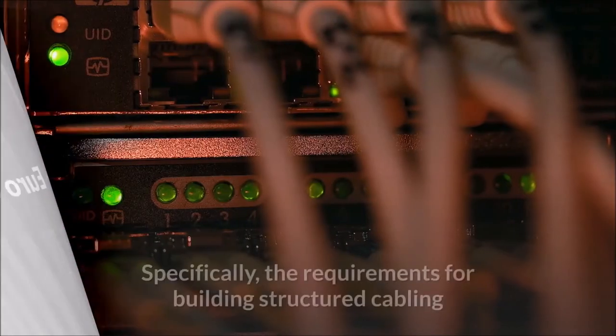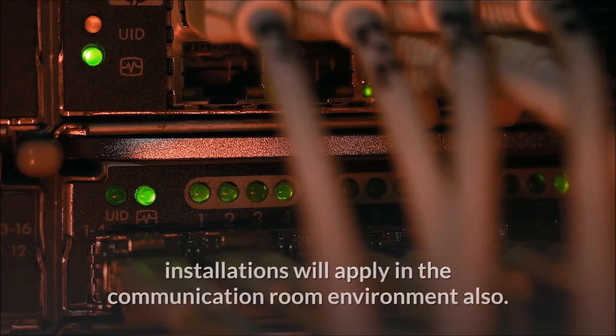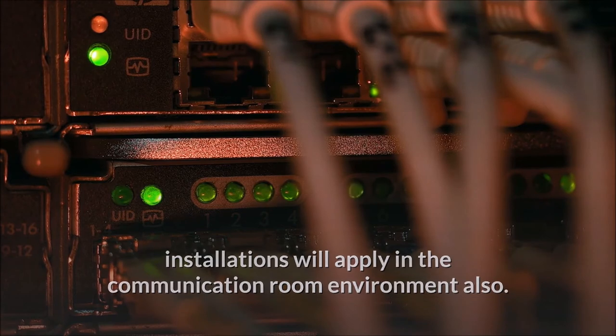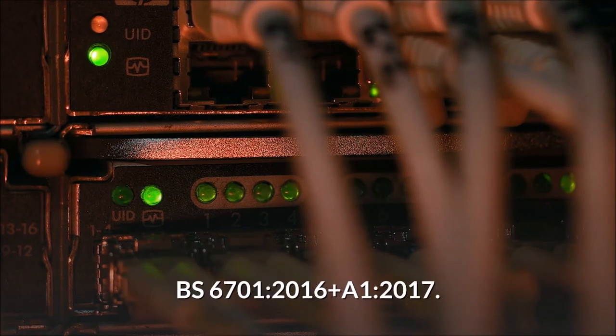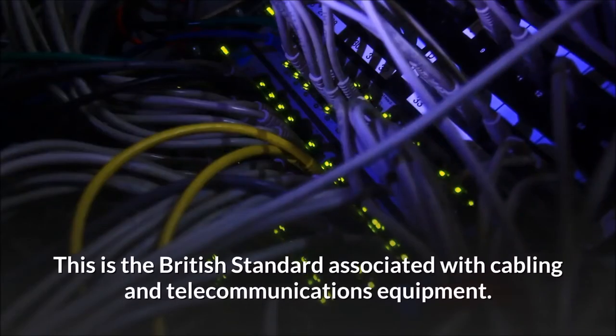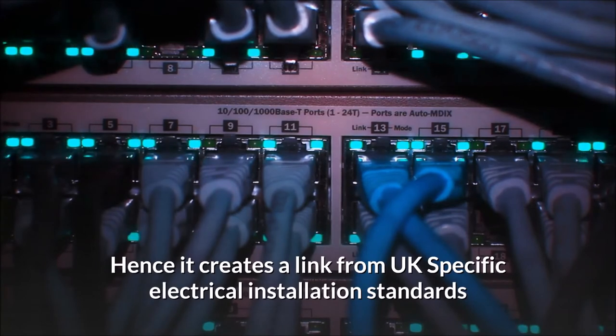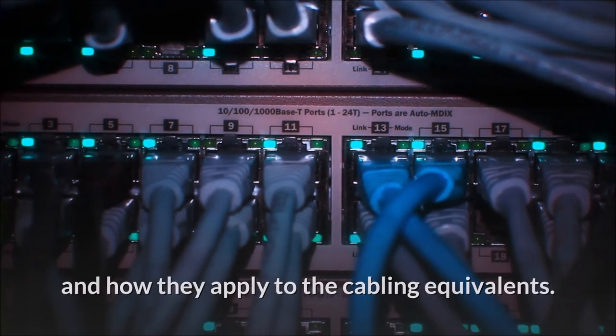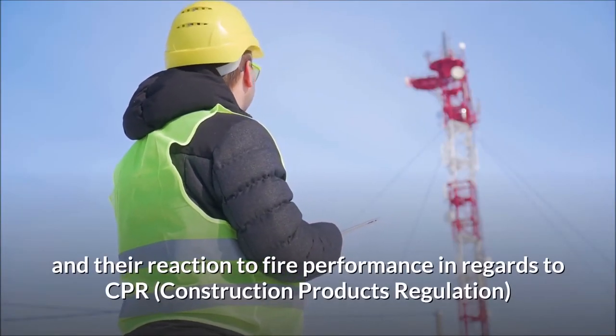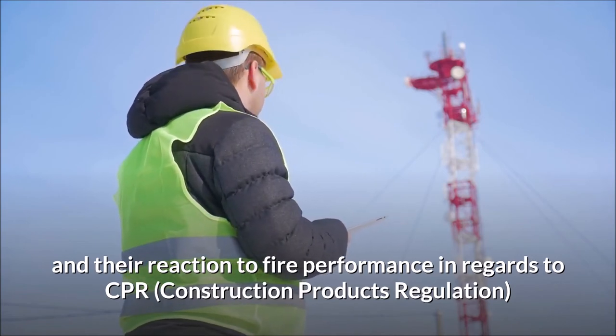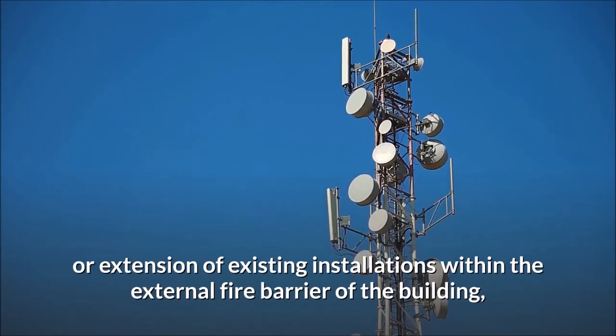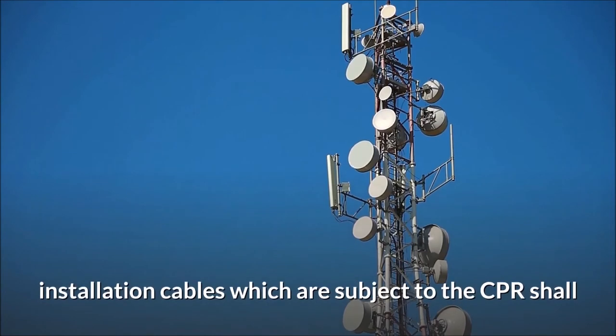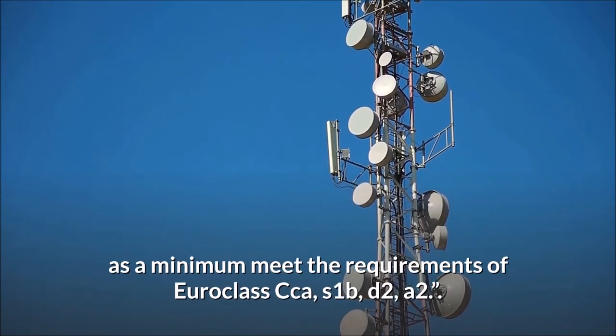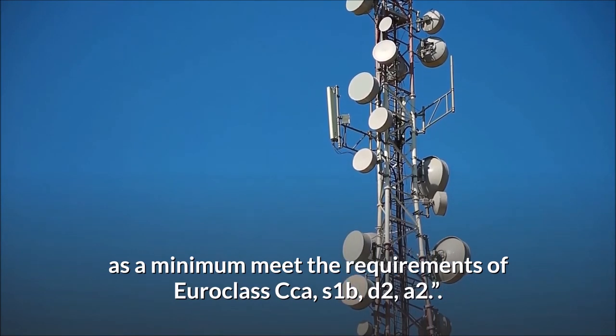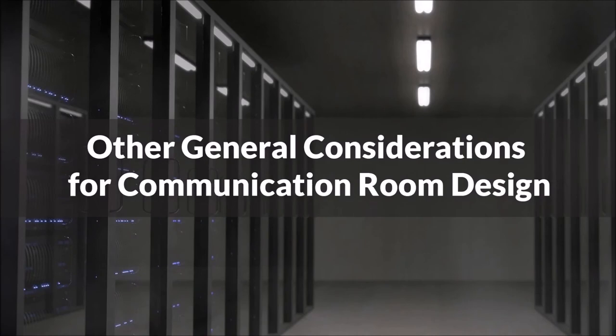Euroclass data cabling. Specifically, the requirements for building structured cabling installations will apply in the communication room environment also. BS 6701:2016 plus A1:2017. This is the British standard associated with cabling and telecommunications equipment. Hence it creates a link from UK-specific electrical installation standards and how they apply to the cabling equivalents. It references telecommunication cables and their reaction to fire performance in regards to CPR, construction products regulation, for new installations and the refurbishment or extension of existing installations within the external fire barrier of the building. Installation cables which are subject to the CPR shall as a minimum meet the requirements of Euroclass Cca-s1b,d2,a2.